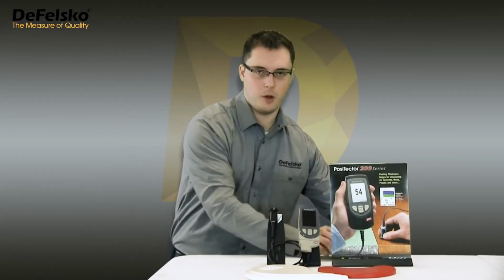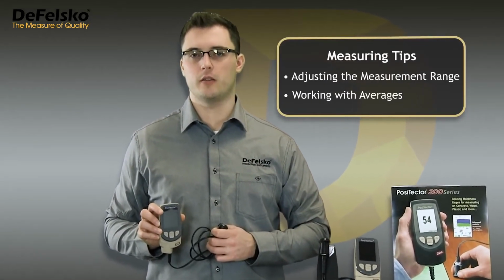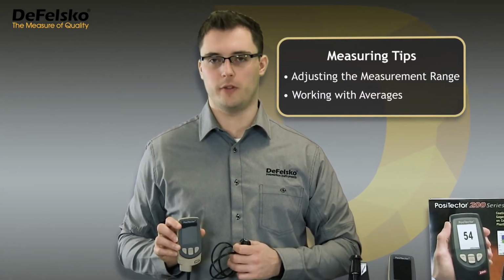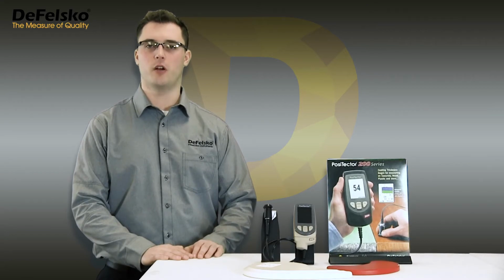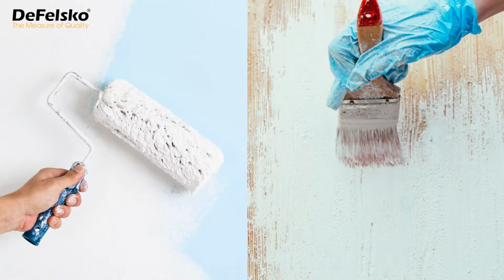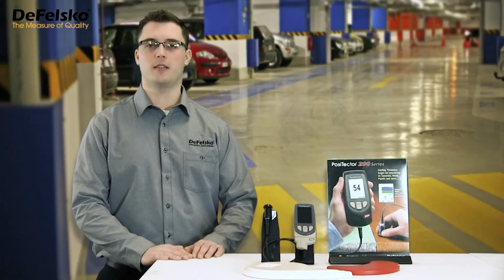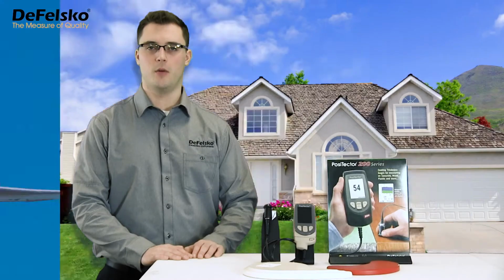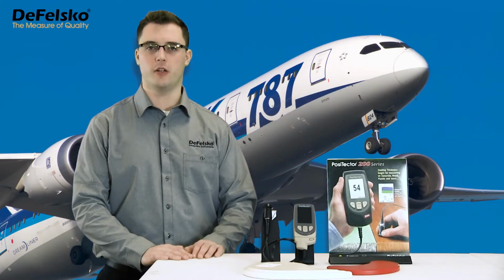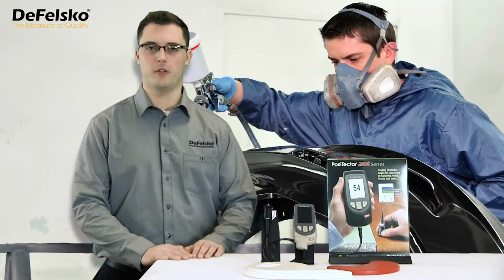By design, the PosiTector 200 is well equipped to handle these situations. In this video, we discuss two techniques for measuring coatings with rough surfaces. Rough or textured coating surfaces are often the result of the brushing, rolling, or spraying application method. Sometimes texturing is deliberately produced for reasons such as creating a non-skid surface, cooling structures by reflecting the sun's rays, protecting advanced fabrication materials, sealing and waterproofing rough substrates, or simply for aesthetic reasons.